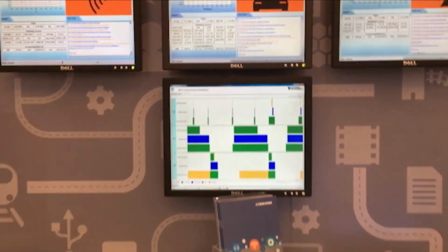So this example of the virtual instrument feature is about sharing RF resources, not just across devices, but also across test clients. And in doing so, making sure that the instrument is operating with the maximum utilization 100% of the time. I can show you that in a little bit more detail by showing the graph utilization on the WTS if you come this way.